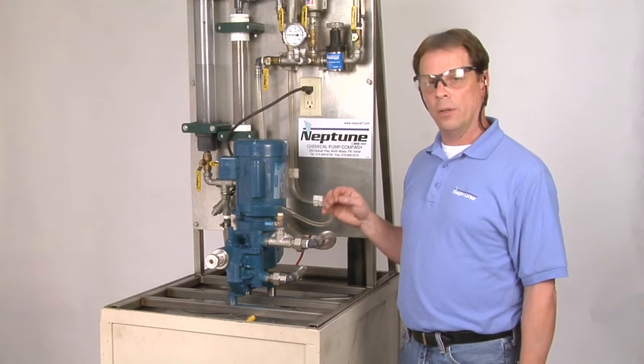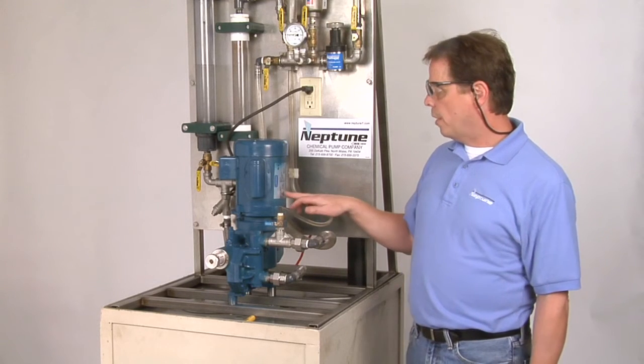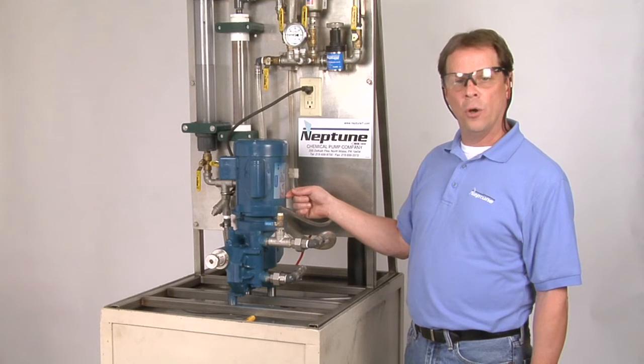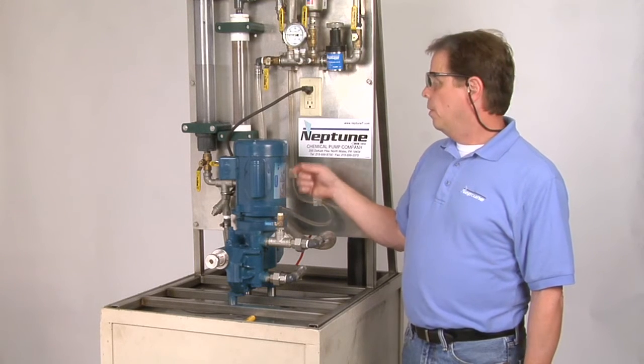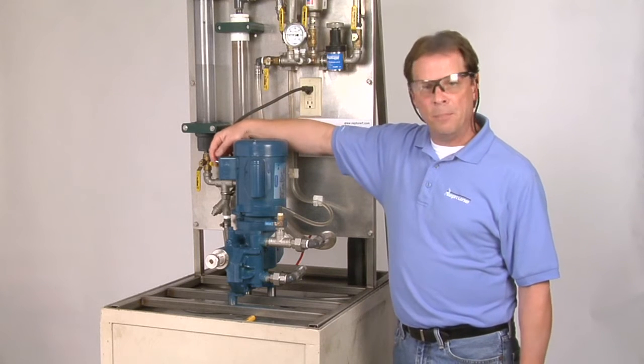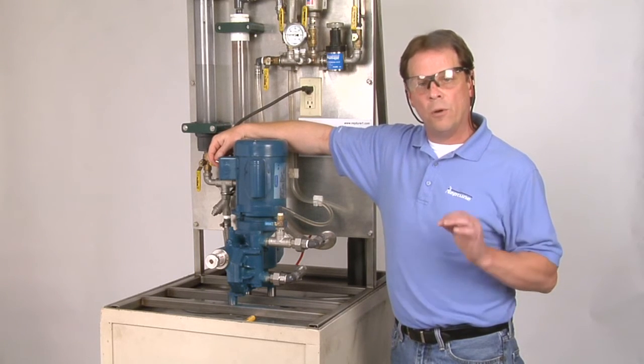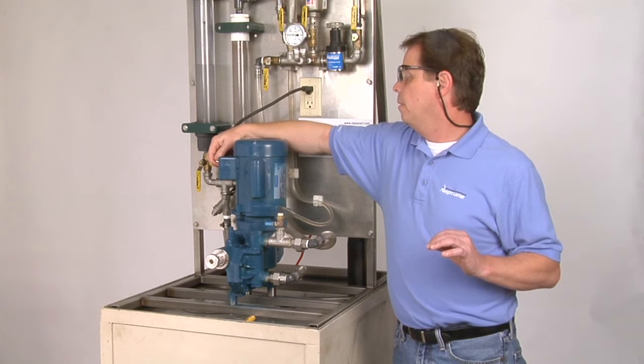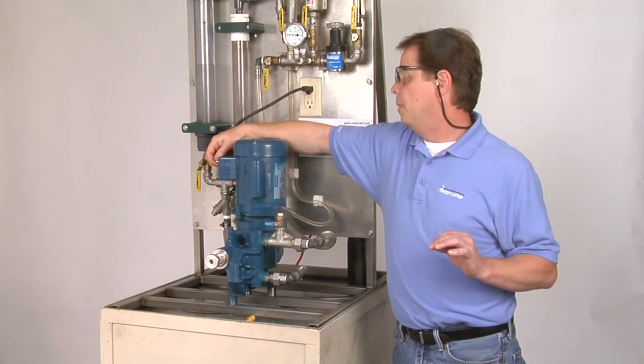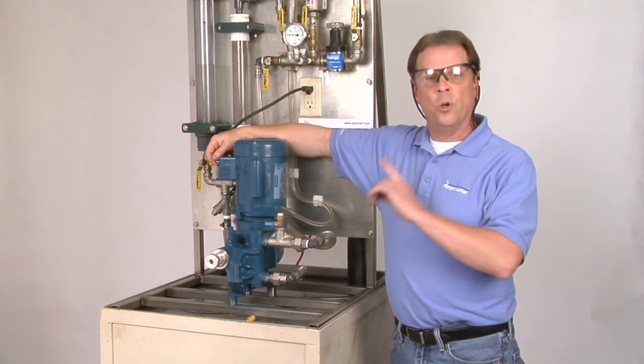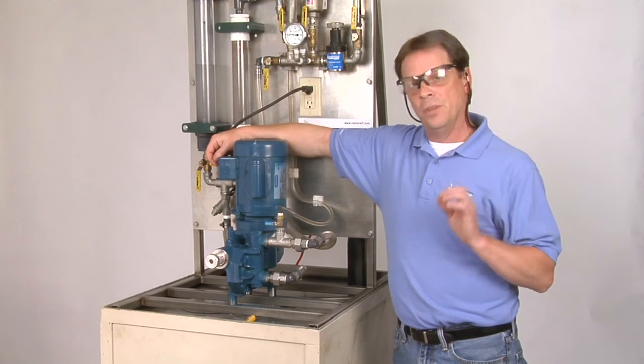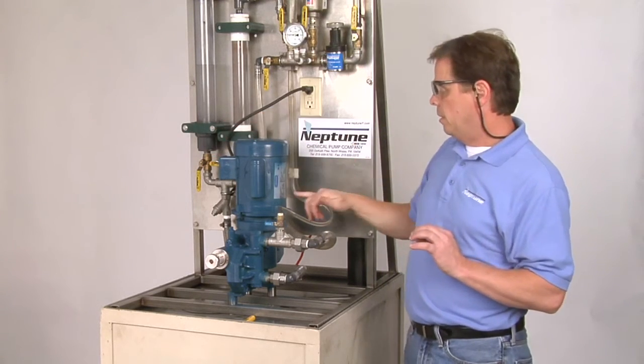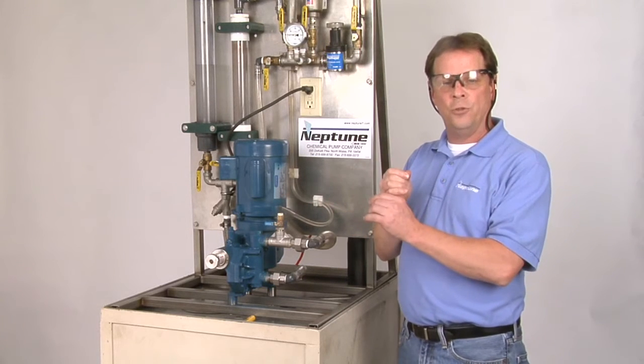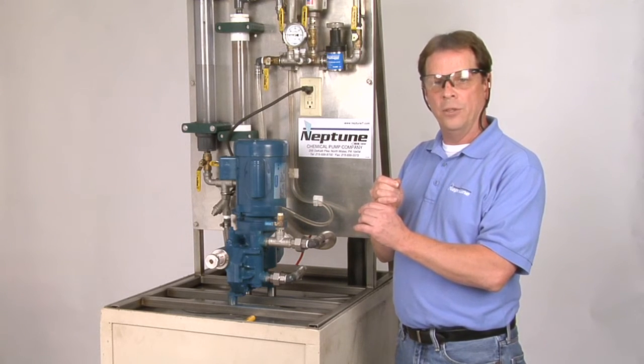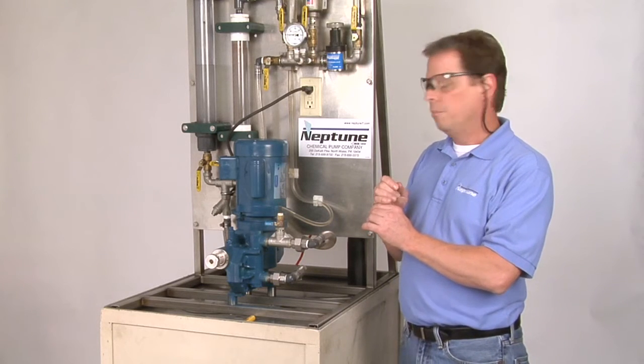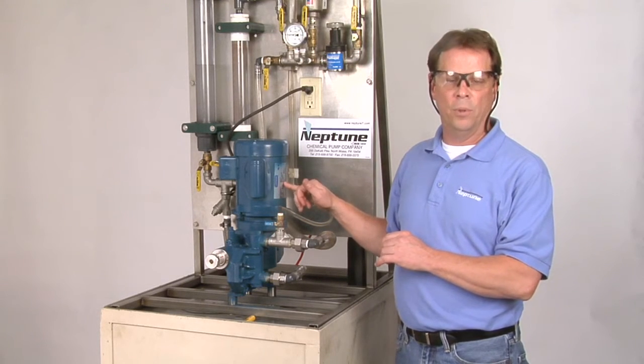It needs to go in a counterclockwise rotation. Once you wire up your motor, the schematic is typically on your motor label. You bump it. When I mean bump, you just turn the pump on and off real quick to get your rotation. Now you can't see in the camera frame, but it is going in the counterclockwise rotation. If it's not going in the right rotation, typically all you need to do is interchange two wires to change the rotation on your motor. And again, it should be on your label on how to do the wiring.